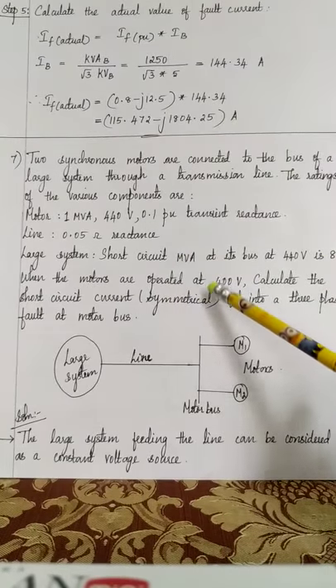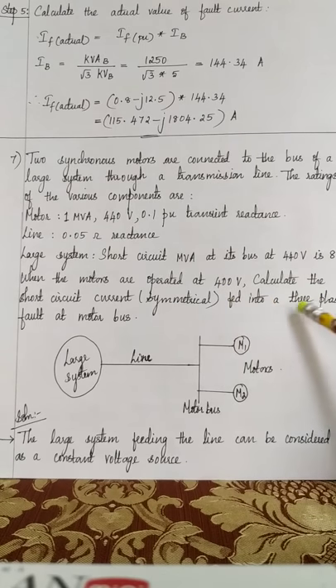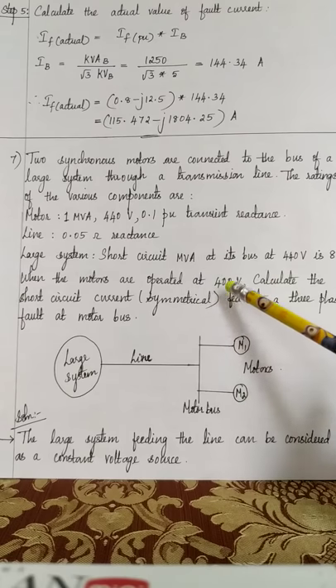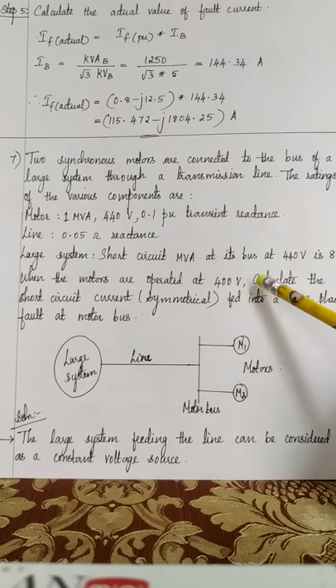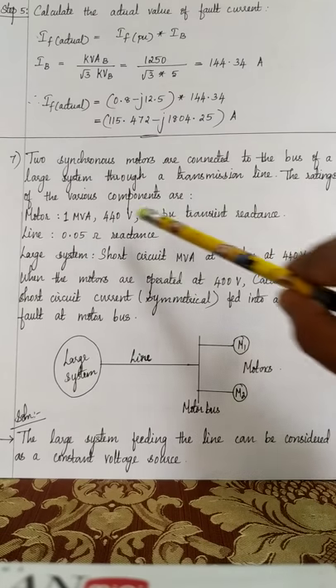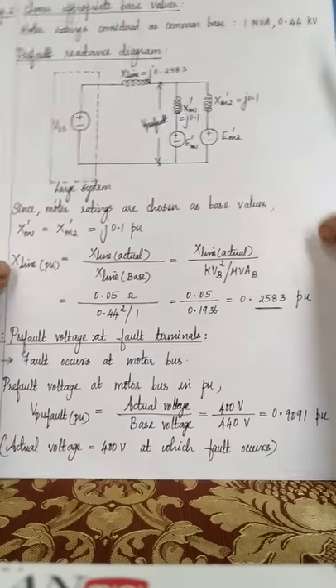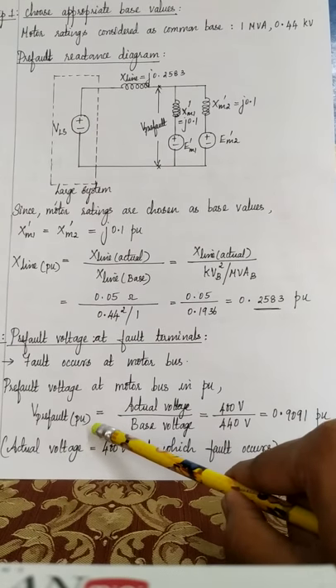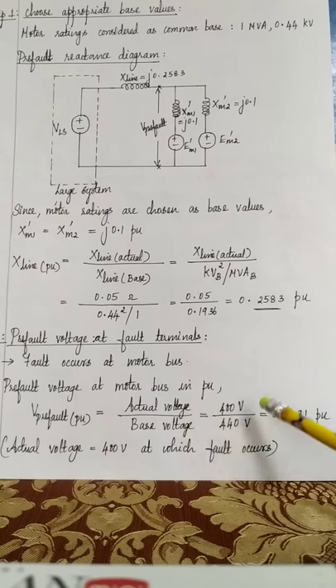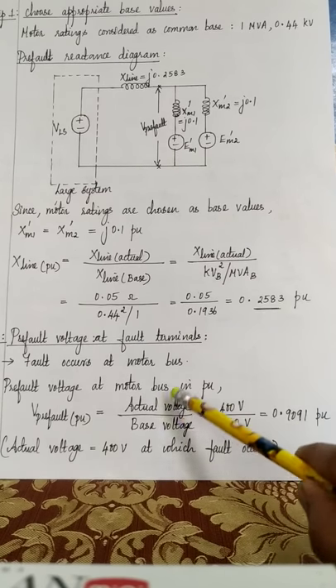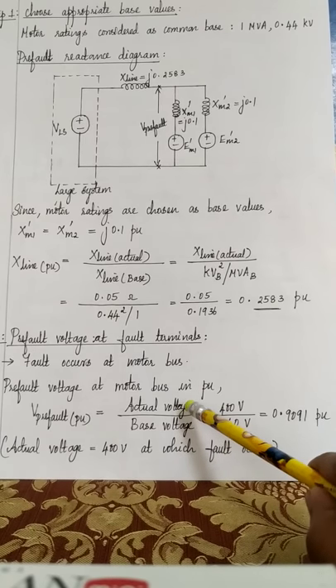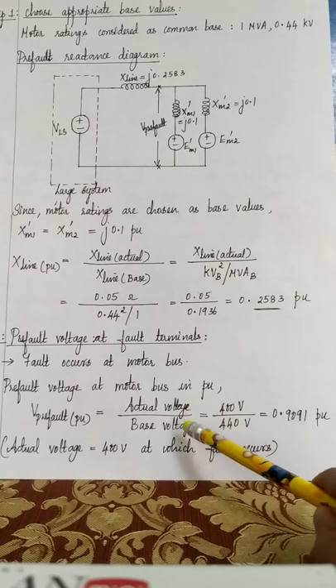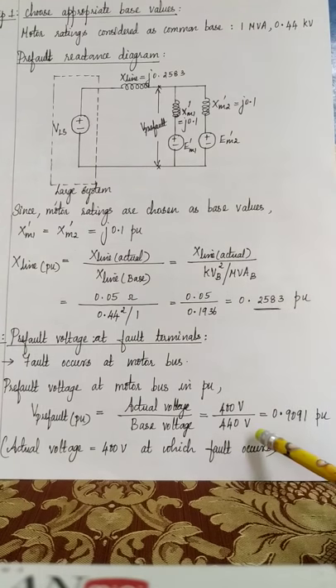So when the motors are operated at 400 volt, a fault occurs. The actual voltage of the motor at which the fault occurs is 400 volt. And what is the base voltage? It is 440 volt. So the prefault voltage across the faulted terminals is actual by base voltage, which is 400 by 440. Here again we should be careful: the actual voltage at the time of fault occurrence is 400 volt, and the base voltage of the motor is 440 volt. So we got the per unit value of prefault voltage as 0.9091 per unit.